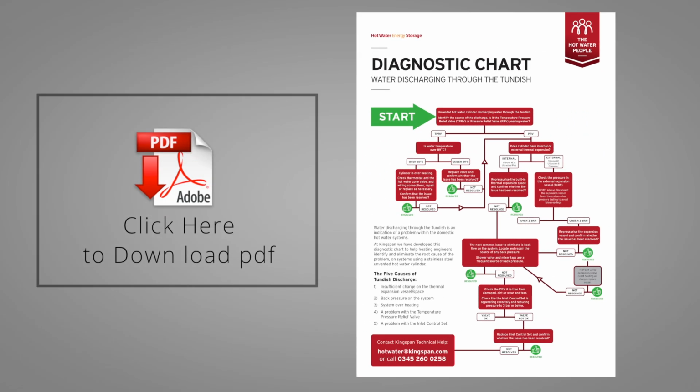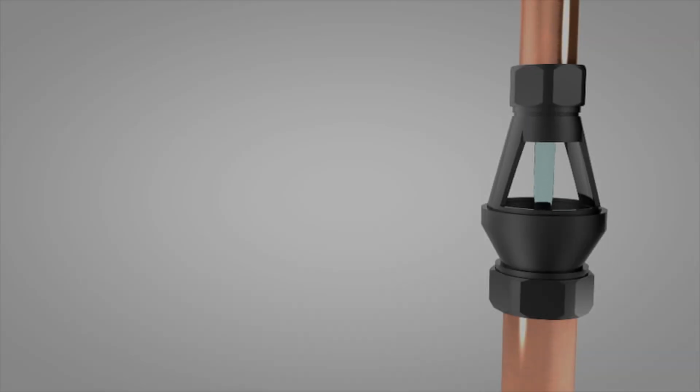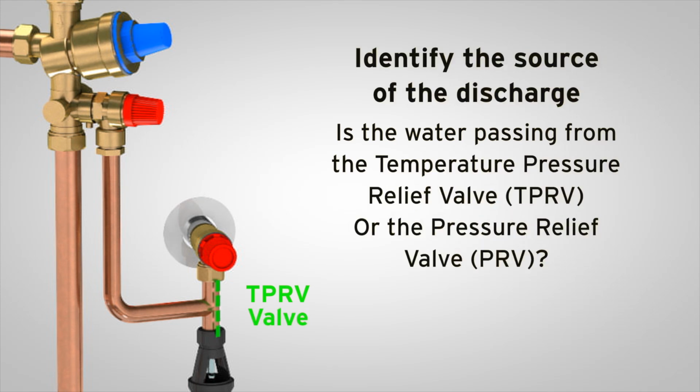A PDF download of the diagnostic chart is available on the link below. First, you must identify the source of the discharge. Is it the TPRV or the pressure relief valve, or PRV, passing water?